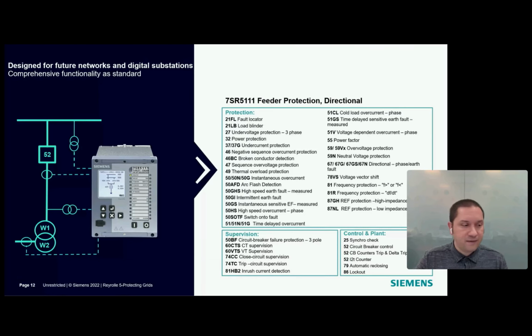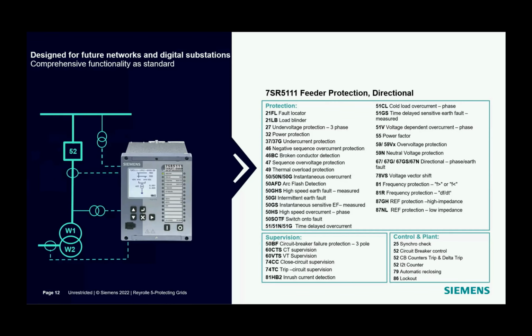Measured and calculated earth fault protection elements provide a flexible solution when both earth fault and sensitive earth fault current detection approaches are required. With the addition of voltage inputs, the device has all of the associated protection functions. Likewise, 67 directional overcurrent protection, which allows each overcurrent and short circuit stage to be set to forward or reverse direction. 27 undervoltage and 59 overvoltage protection, or 78VS vector shift, 81O and 81U over and under frequency protection functions, and also 81R frequency rate of change protection functions are available as standard.